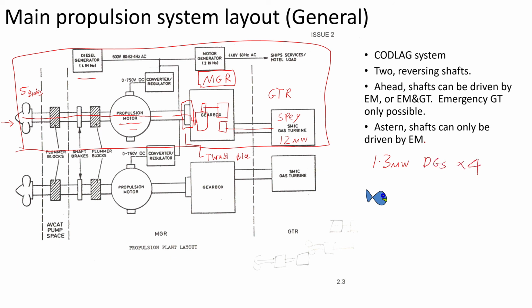Times 4, and they provide power at 600 volts and about 62.4 hertz to a 600 volts 3-phase bus. Now, that 3-phase bus provides power to the converter regulators. There's one thyristor converter regulator per electric motor, and that drives the propulsion motors.